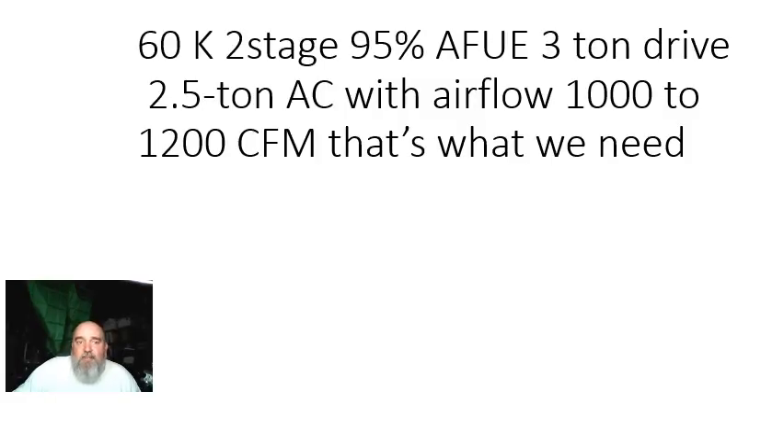We have chosen a 60,000 BTU, two-stage, 95% AFUE furnace with a three-ton drive in it. It's going to get paired with a 2.5-ton air conditioner that has airflow anywhere between 1,000 and 1,200 CFM. The 1,200 CFM is going to meet our sensible, meet our latent, meet our total. At 1,000 CFM, it's covering 90% of our sensible, not 100% of it, but it's okay.